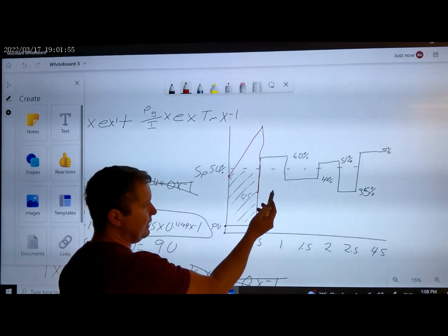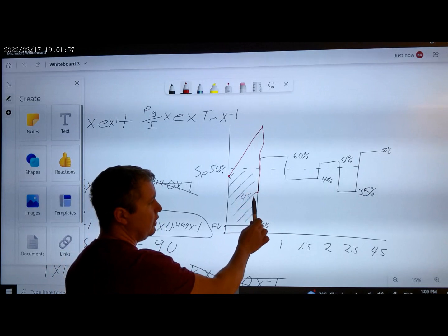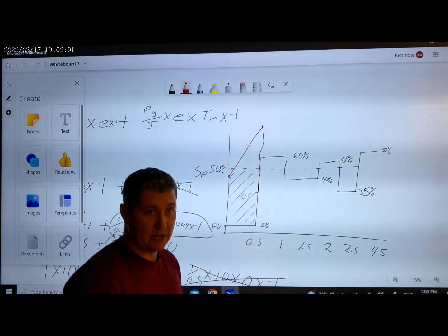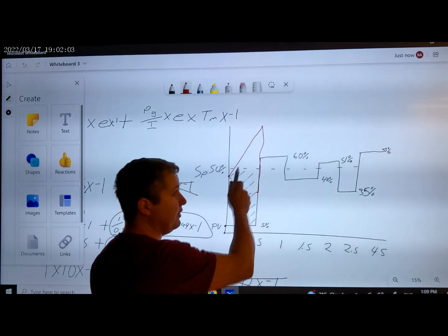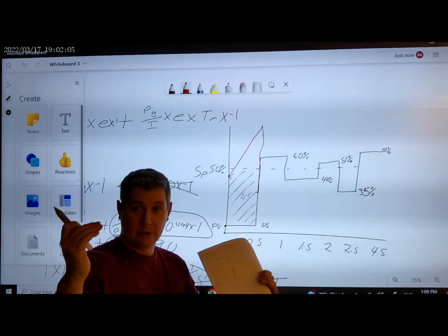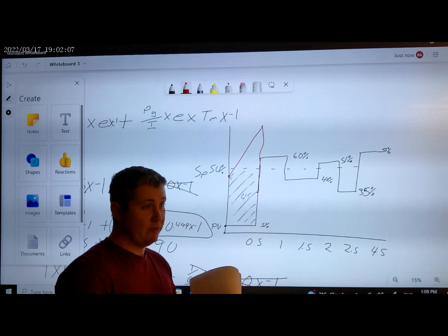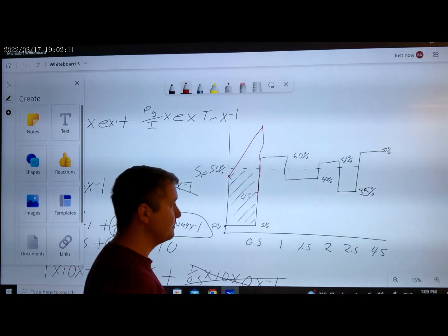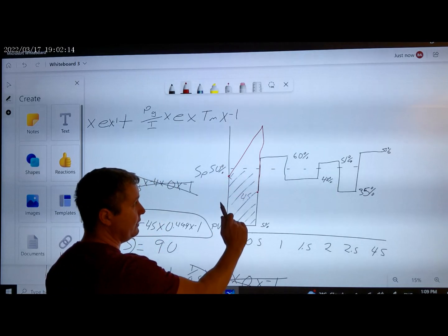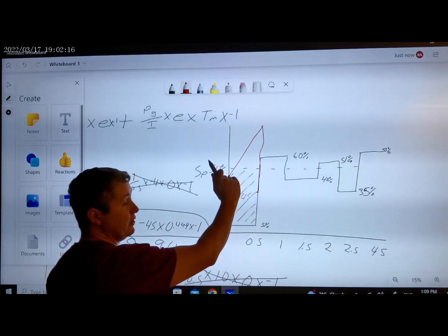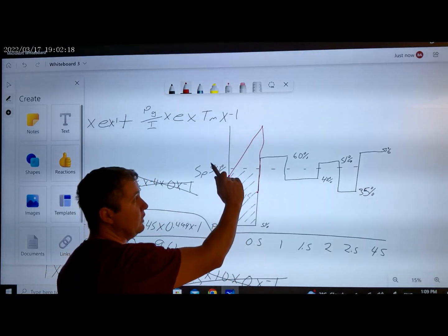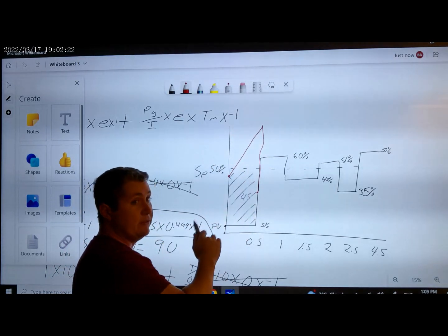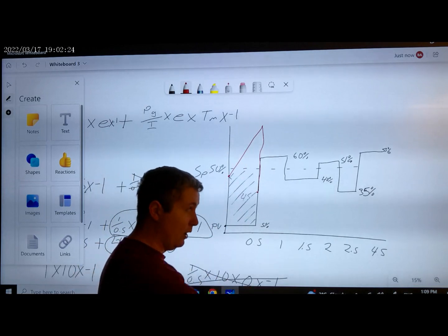Because, and that makes sense, our output increased, and so let's say it's our variable frequency drive. Well, now we've gone above our set point. We want to turn our variable frequency drive almost off, right? Because now we're above our set point. When we were below our set point, we turned our variable frequency on. That's what the controller did, and it said, you're not getting back to your set point, so I'm going to keep increasing the speed of your variable frequency drive, causing more water to go in.